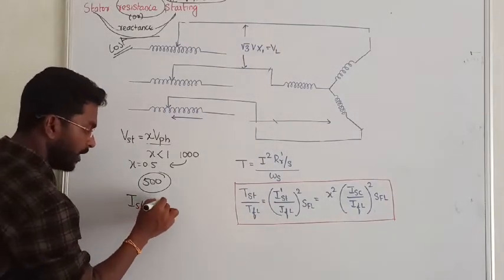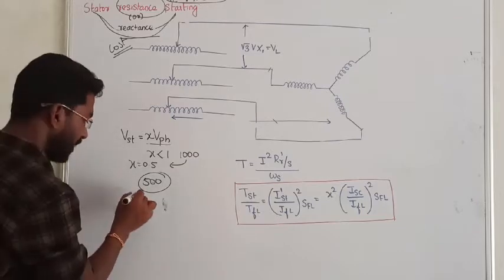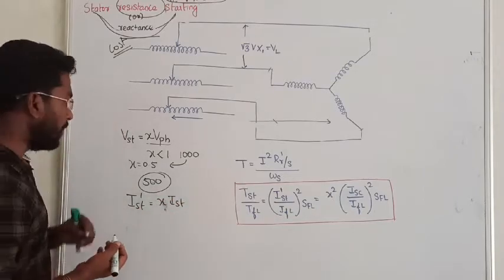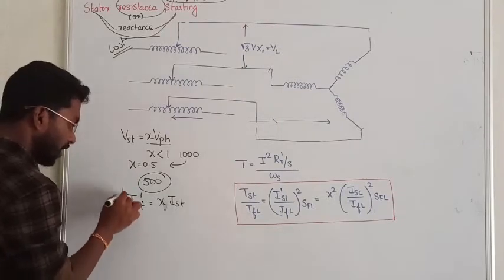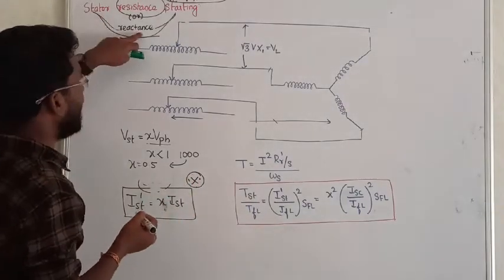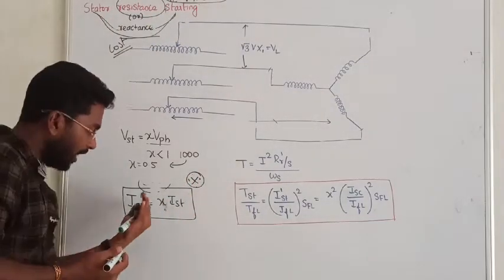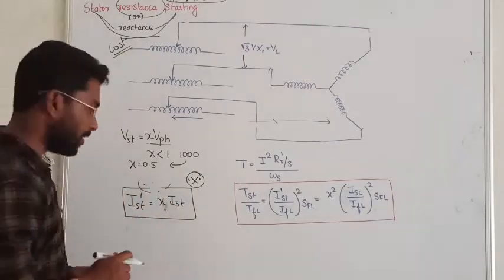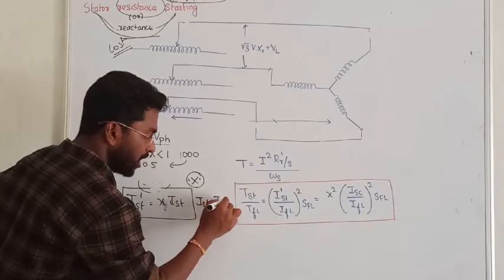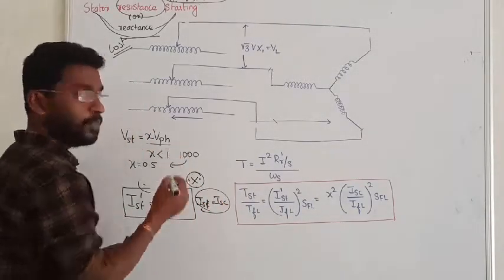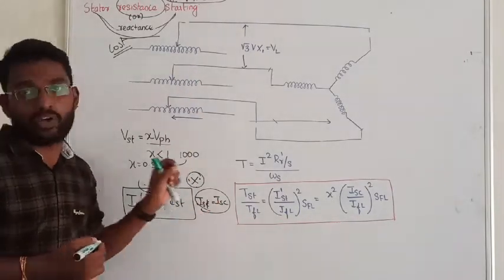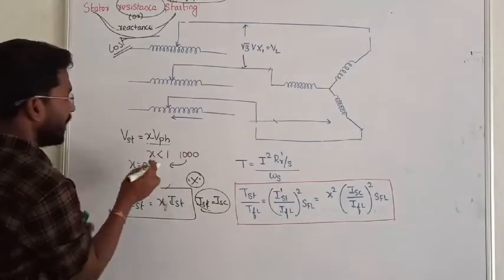Since the starting voltage is reduced by X times, the starting current is also reduced by X times. We represent the reduced starting current as Is-dash, which equals X times the actual starting current. This is very important. The starting current can also be called the short circuit current, because at the time of starting, slip is 1 and the rotor is effectively short-circuited.